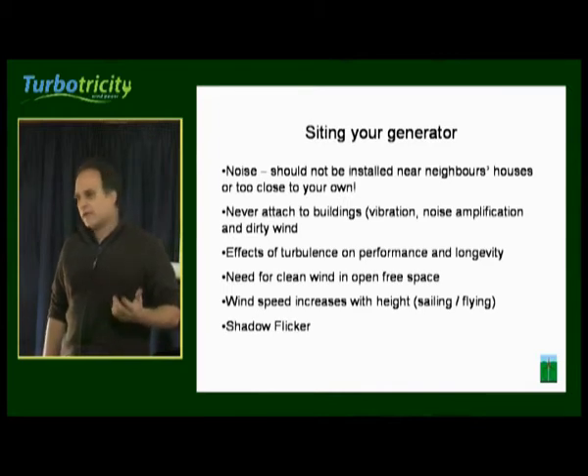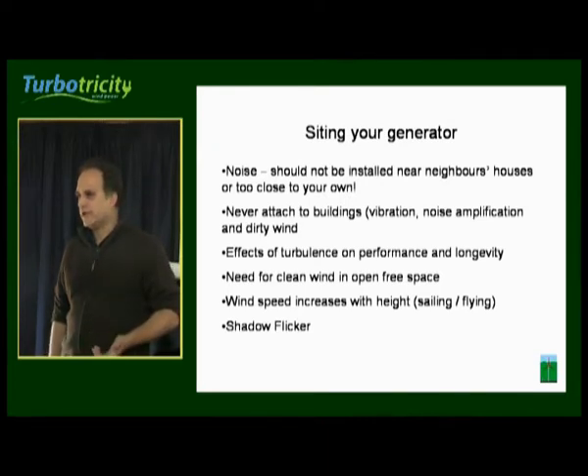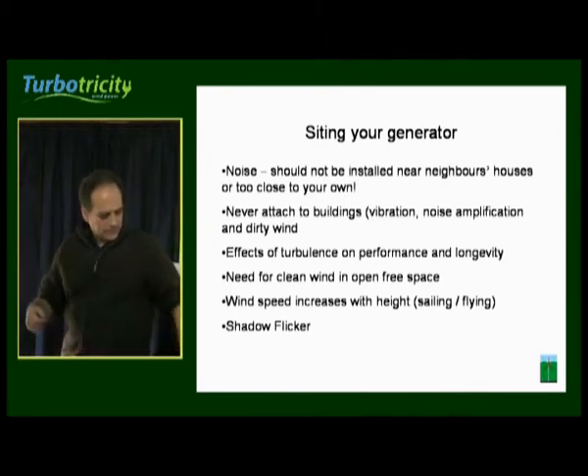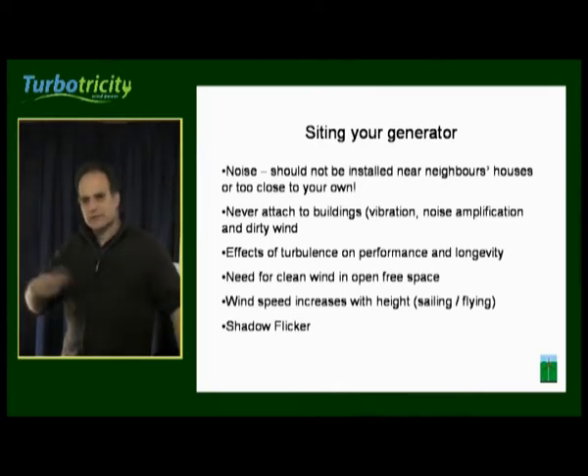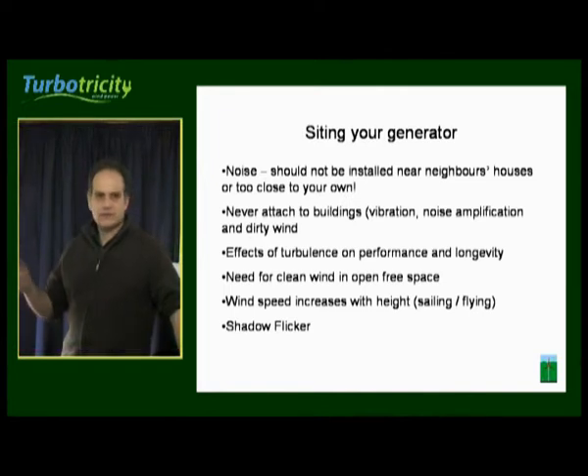It should never ever be attached to the building. I know they sell turbines that are attached to buildings, but first of all, concrete is not a tensile material — it doesn't have tensile strength, it's not designed for it. But principally, there are resonances that come down a turbine, depending on the speed that it's running at, there's a natural frequency coming out of the turbine.